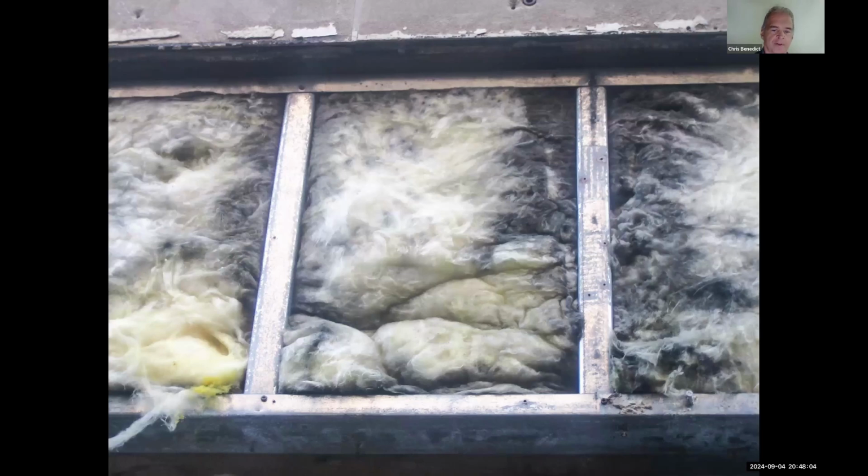Here's fiberglass insulation that was behind, like, above a storefront. The sign was there, and they took the sign down, and you see that for a long time air has been leaking through the fiberglass insulation. Some people call it filter glass because it's not a barrier to air leaking at all. So when you see a window being installed with a huge gap between the window and the wall, and people put fiberglass in there, that's a waste of fiberglass. It's not stopping the air leaks.